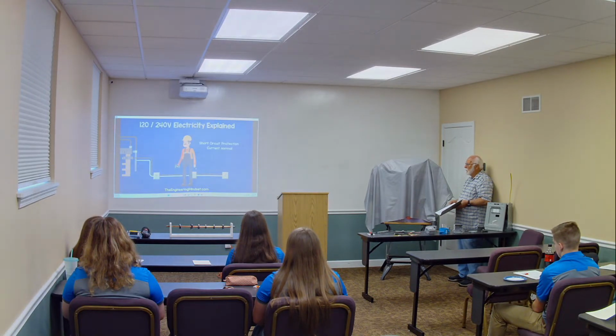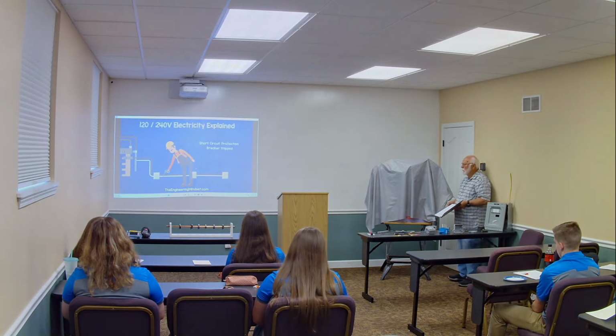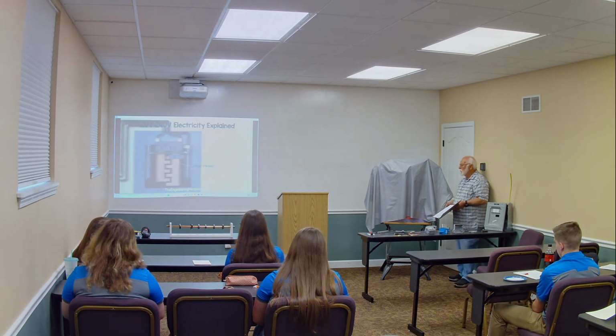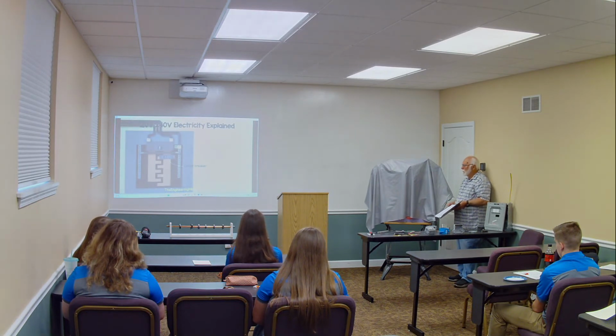The second feature is short circuit protection. When the hot and neutral come into direct contact with each other, the current will dramatically increase, almost instantly. When this occurs, it creates a magnetic field which will trip the breaker and cut the power automatically. Let's have a look at how the circuit breaker is connected to the electrical circuit. In this example, we will connect to a simple light fitting which is controlled by a switch. We take the hot wire from the circuit breaker and run this to the switch.